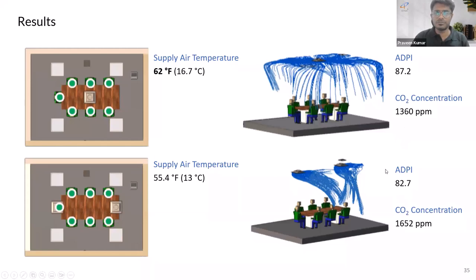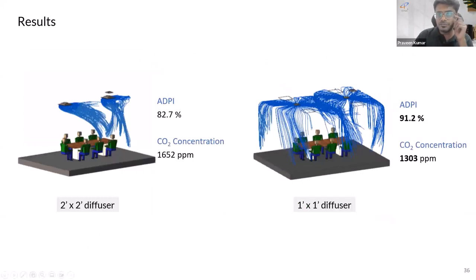So we thought, what if we stick to the same two diffuser pattern but reduce the size of the diffuser, so we could still produce the same throw effect as in the first design configuration. We tried the same design with a reduced size, one by one diffuser, and with that we got an increase in ADPI above 90, which is good, and a good reduction in CO2 concentration, down to about 1300.